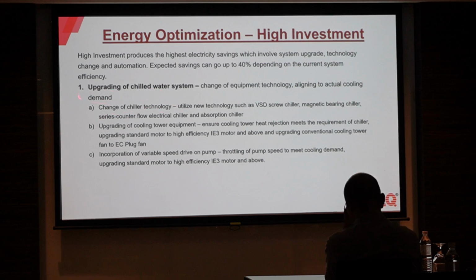So what needs to be done? The first thing is to upgrade the chill water system. We change the equipment technology, aligning to actual cooling demand. So what is the change of chiller technology? With the new technology, VSD plays a big role. Previously everything is constant speed. So now we have this VSD screw chiller, magnetic bearing chiller, series counterflow chiller, and absorption chiller.